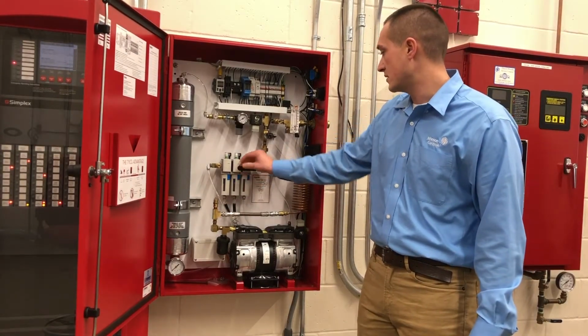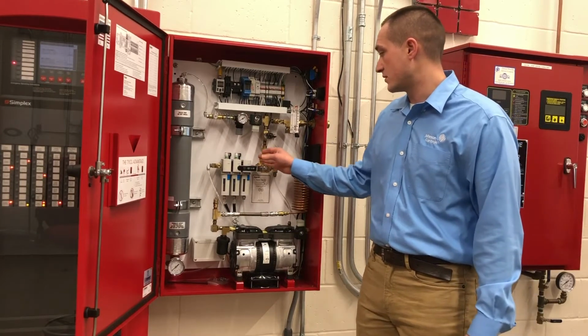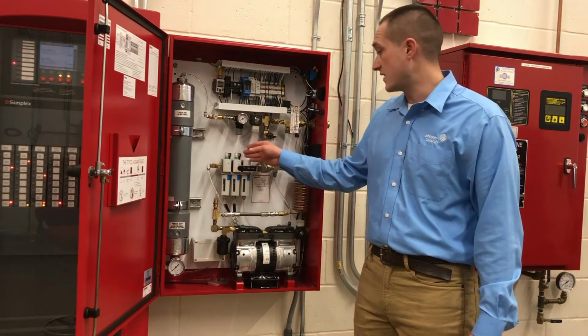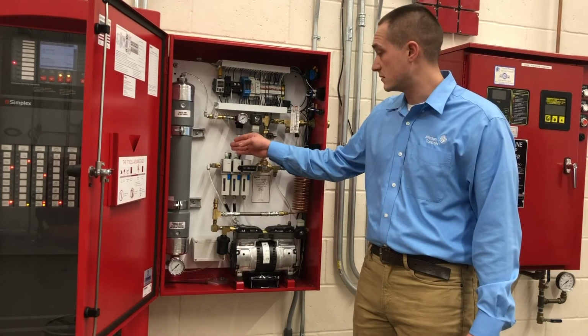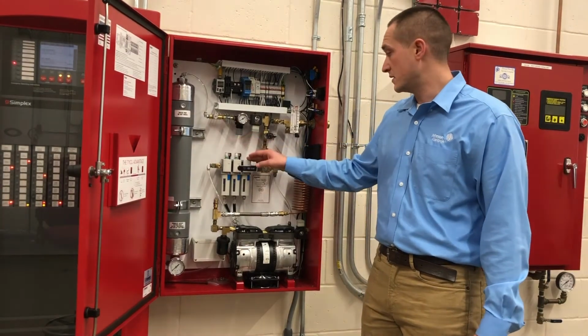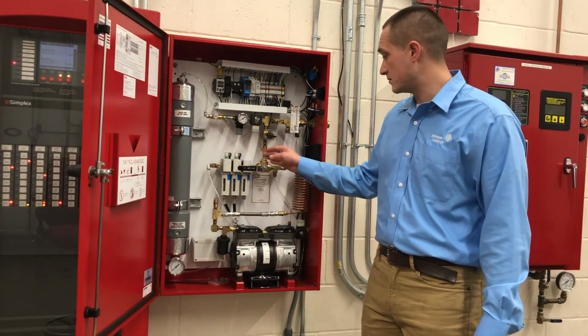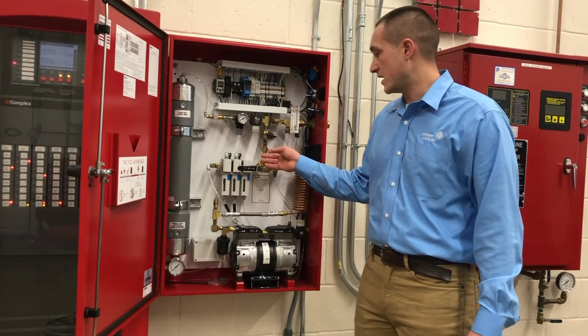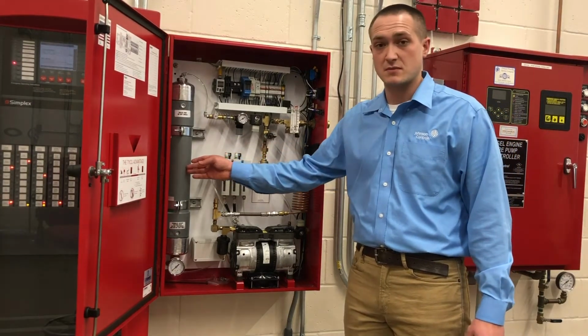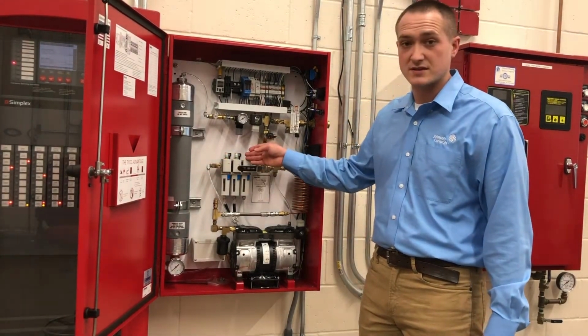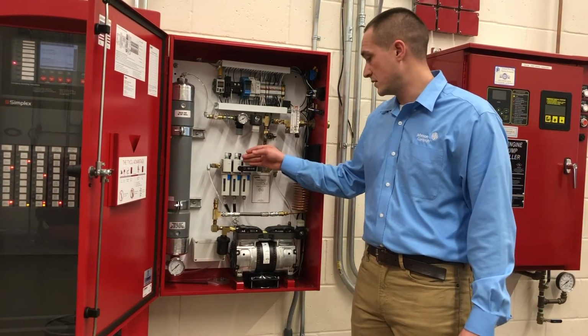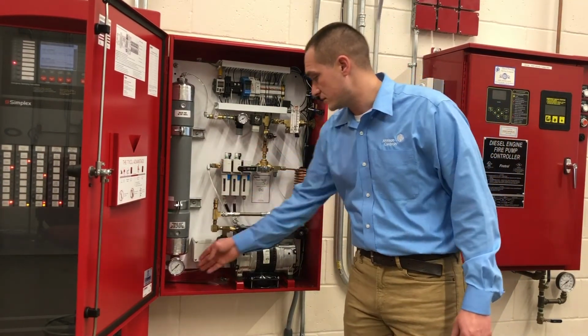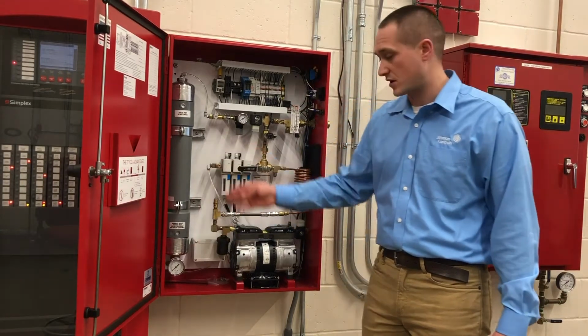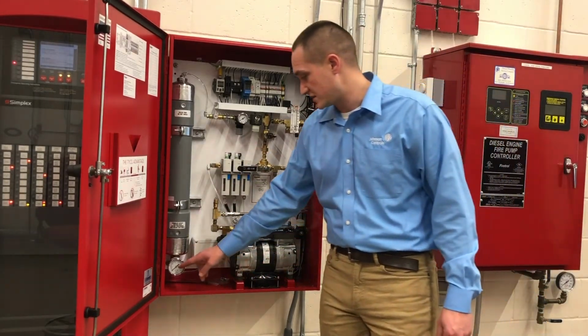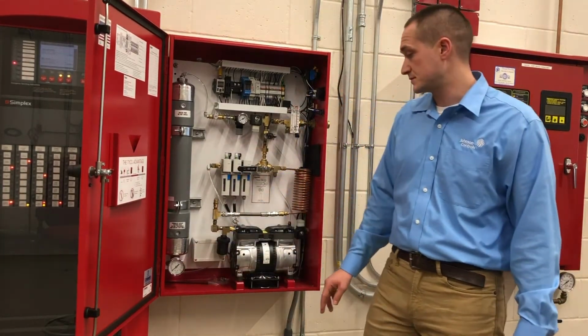In nitrogen mode, we're going to take this air, we're going to bring it through a series of filters. 5 micron, 1 micron, 0.01 micron. This is ensuring that we have a very pure air source for our separation membrane. It's going to remove any particulates or any water vapor. That air is then coming through to the inlet of our separation membrane. This pressure gauge helps us during troubleshooting.